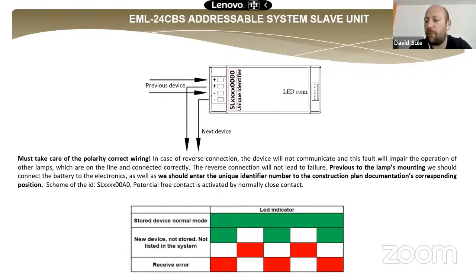Not only the panel and the programming software can show the error of the lights. All of the emergency lights and exit lights have a status LED indicator inside the box. We can see it from outside the light box. It can be red and green, different combinations about the status. So if the light is programmed by the panel, it's found by the panel, and the communication is okay, that will be a steady green. So it's a stored device with normal communication.